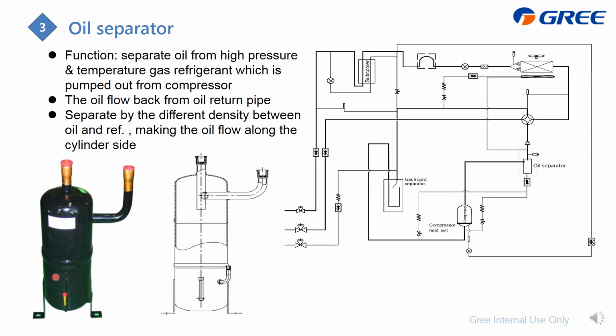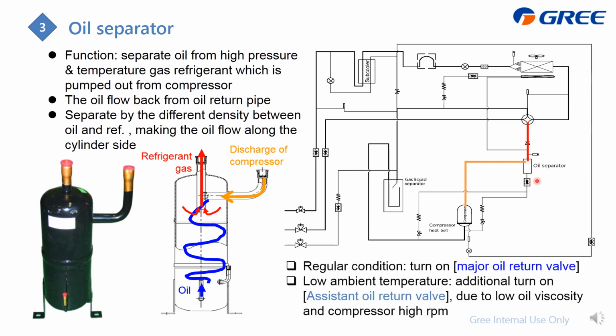Here is the appearance. The gas in here, after separation, will flow out from here. And this one is the oil. And here is how it will operate. And also the oil, which is from here, you have two passes. The first is the major oil return, which is this one, in any condition, either cooling or heating, it will always be on to conduct the oil flow back to the compressor.